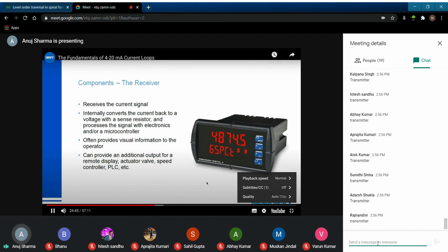That's the job of the transmitter and the power supply. One thing to note is that often either the transmitter or the receiver will have a power supply built into them, which is why sometimes you don't need a separate one. The panel meter shown here, for example, is a Precision Digital ProVu panel meter. If you're powering it from a separate DC or AC voltage, it includes a 24-volt power supply that's isolated from that other supply for you to use in powering your loop.